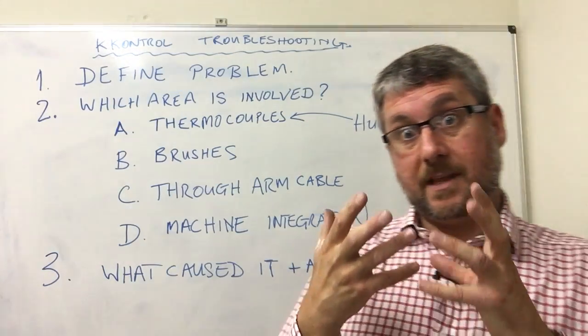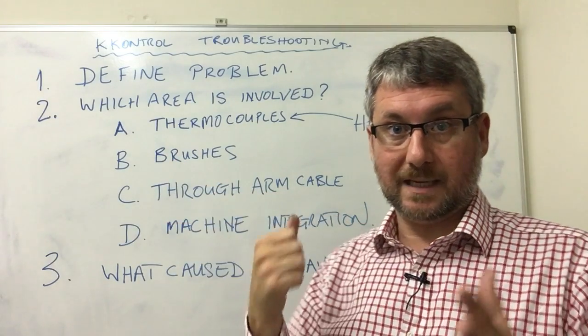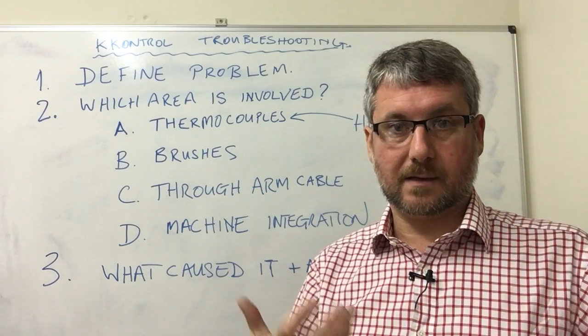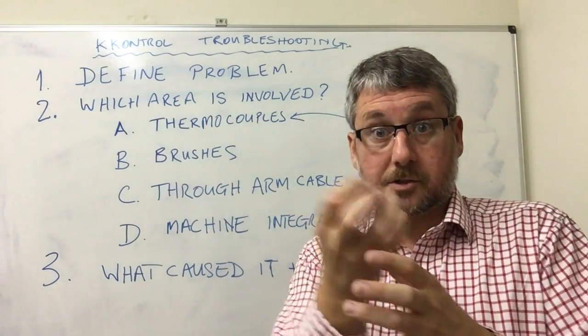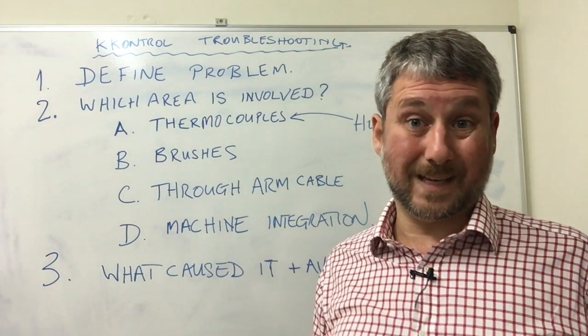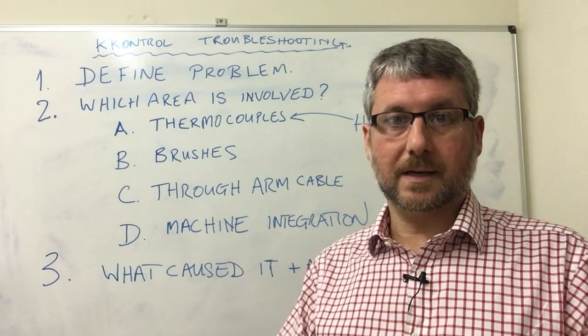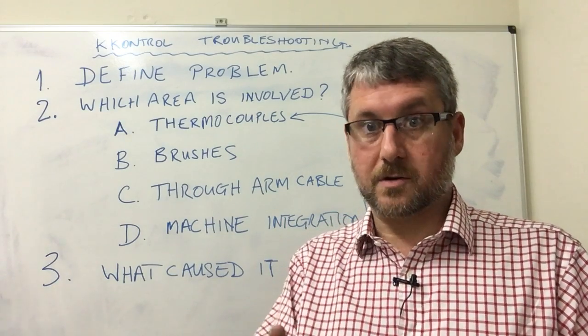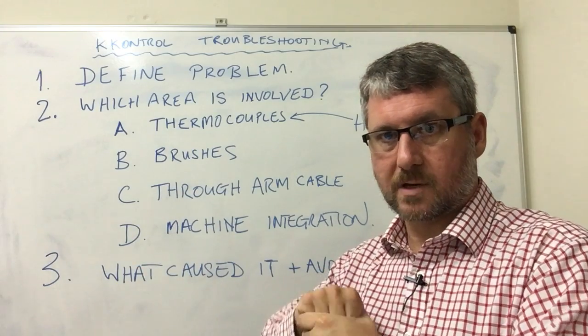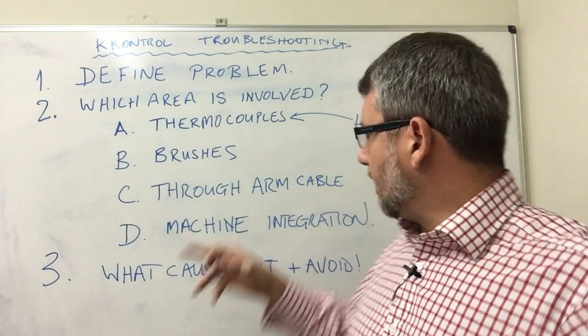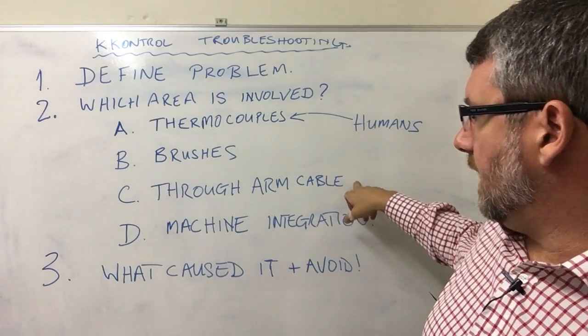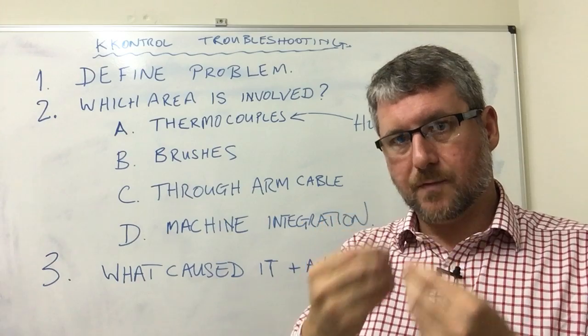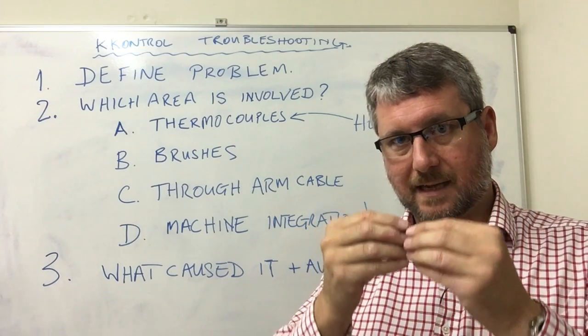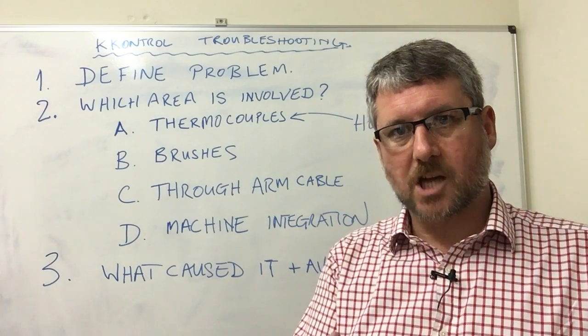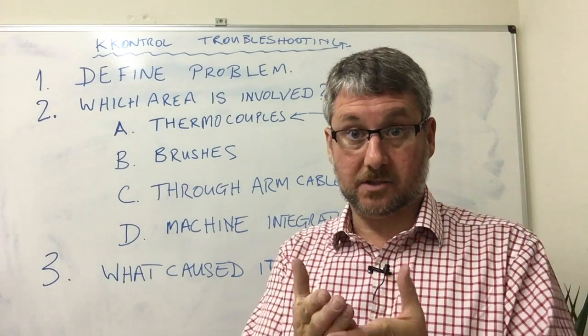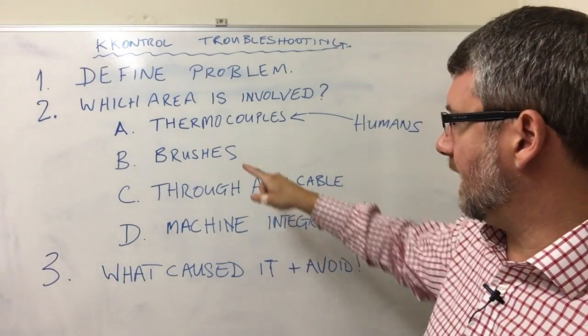The other cause for a lot of problems with brushes would be if someone strikes the slip ring with a forklift truck with a mold dropping on it. The brushes could crack inside. There is not really an awful lot we can do about that except to train the operators to highlight the significance and the importance of taking care of the slip ring disc. Okay, so brushes. The other area within these two here, and in fact the third, is where cables are moving. And if cables are moving, they will degrade. They will degrade and either fracture, but more commonly they degrade, break down the insulation, and then touch. Okay, so that is another thing to look out for.